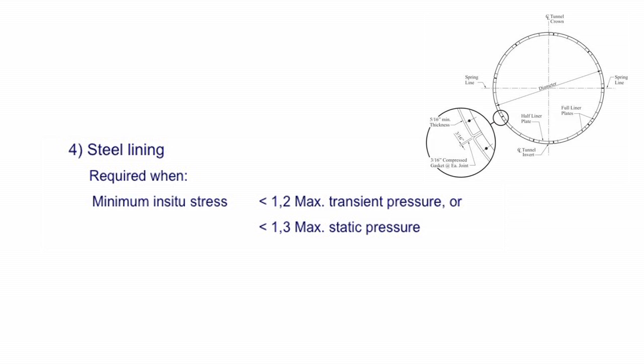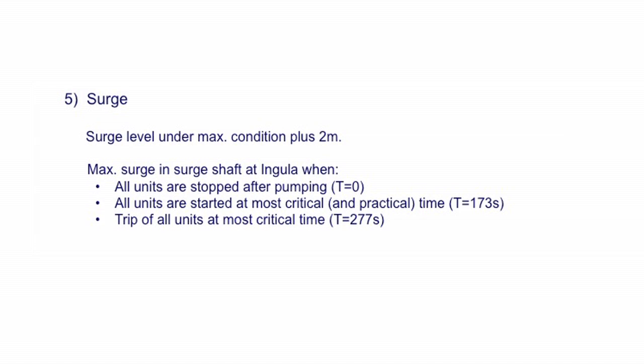Steel liner, there's the factor of safety that we've used, where to use a steel liner, if the minimum in situ stress is less than 1.2 times the maximum transient pressure. That's when a steel liner is required. And we also check it with static pressure. And the surge will only happen when you start up or you stop, any change of flow into your waterways. And there can be various combinations to determine what is the maximum surge.